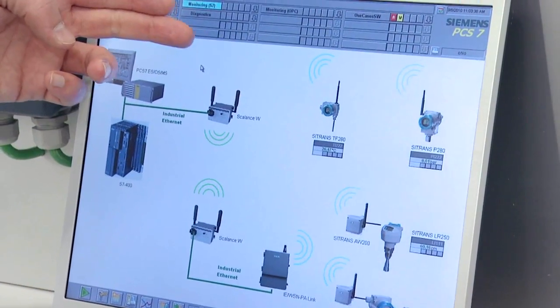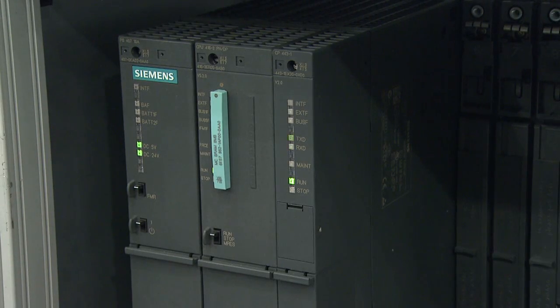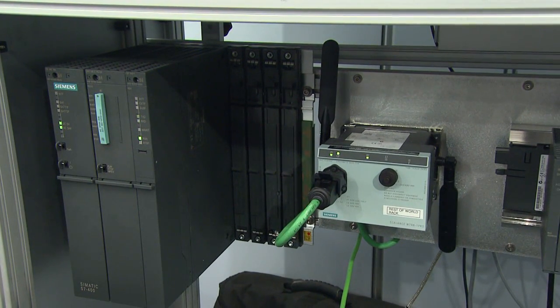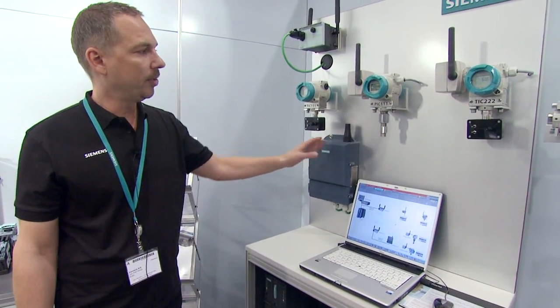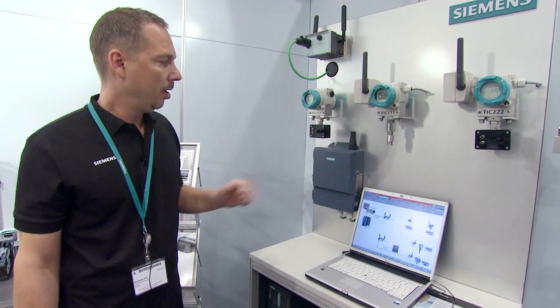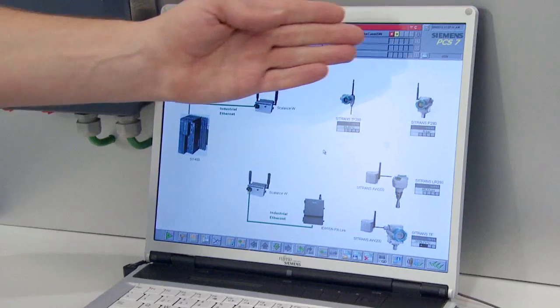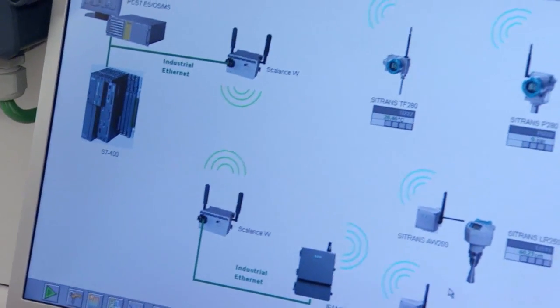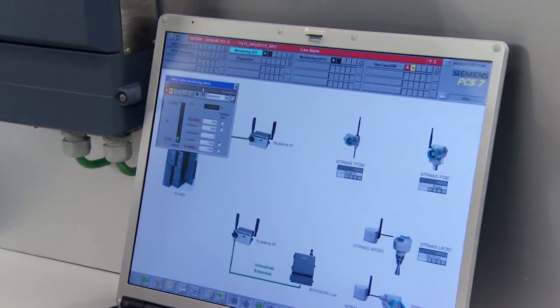WirelessHART can coexist with industrial wireless LAN, so no conflicts can arise. In practice, the brain is down here — our PLC. This could be, for example, the S7-400. It communicates via the access point, which in turn accesses the entire WirelessHART instrumentation, which sends the process values and importantly diagnoses, alarms, and provides the option of being able to change parameters. What you see here is our SCADA system, WinCC, where all of the process values are received. You can also see if there are alarms.